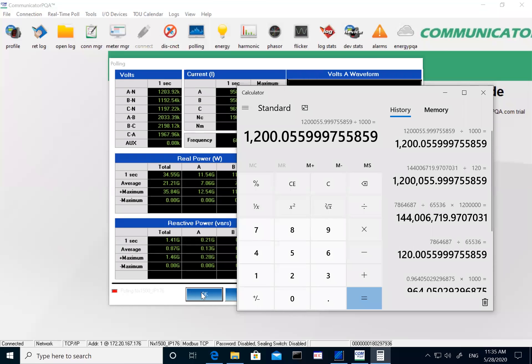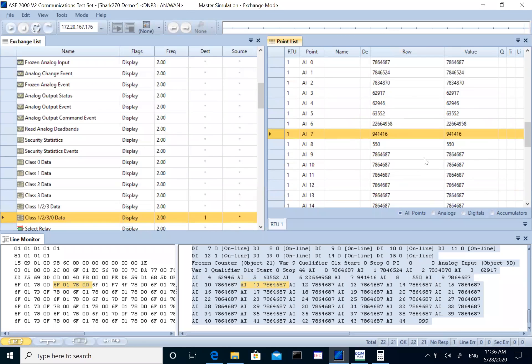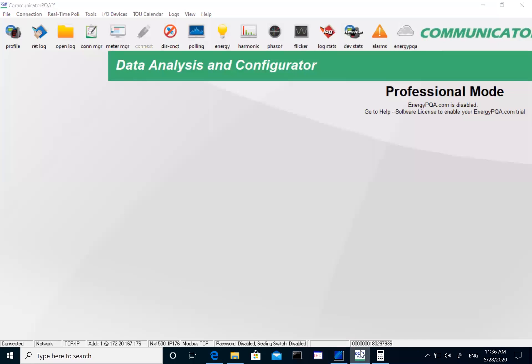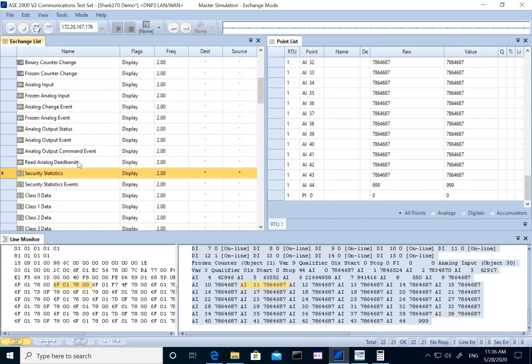I have readings for power factor, frequency, and so on, and you can follow the same similar calculations based on the manual to come up with the correct displayed values. All this calculation I'm doing on the calculator is something you would do on your DNP master or DNP software. To avoid that, you can set up the 16-bit scaling as discussed earlier and scale the meter values according to your CT and PT ratios. Of course you lose resolution fitting 32-bit values into 16-bit, but you can find a balance between range and resolution.